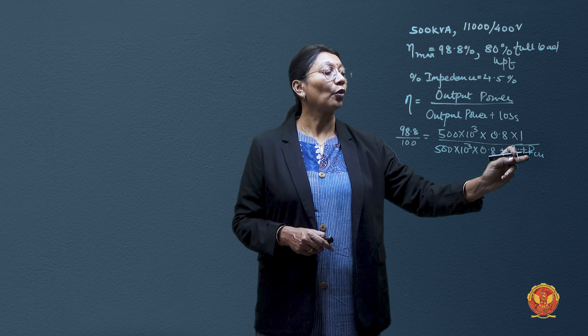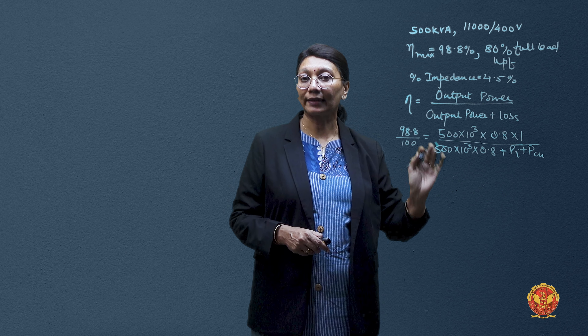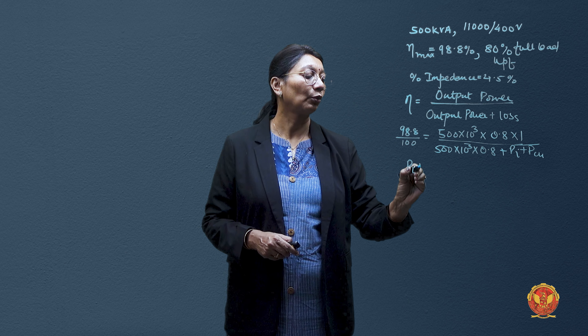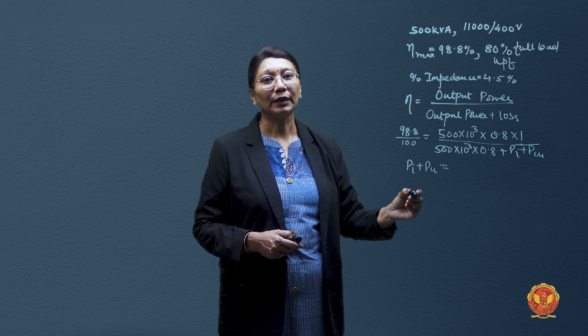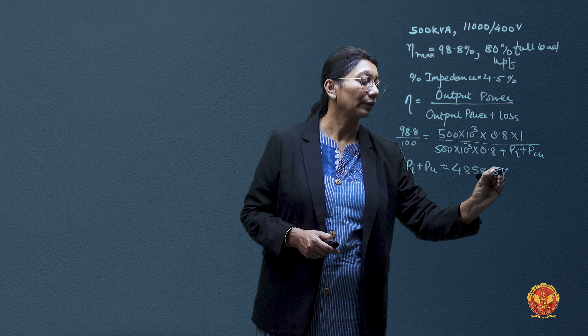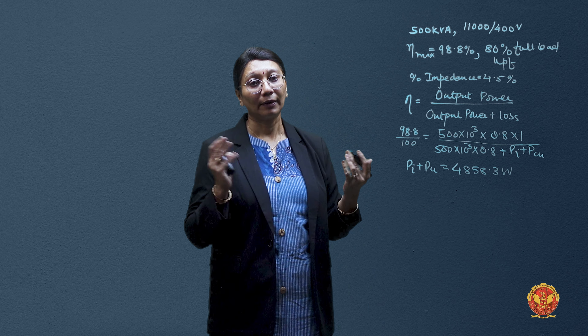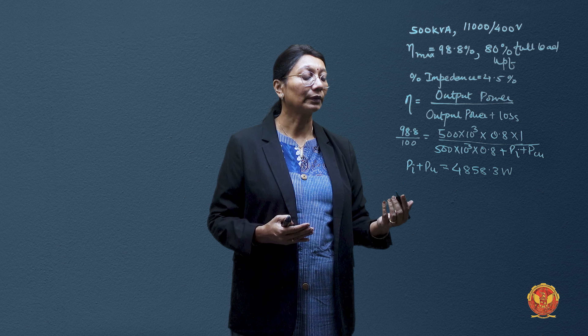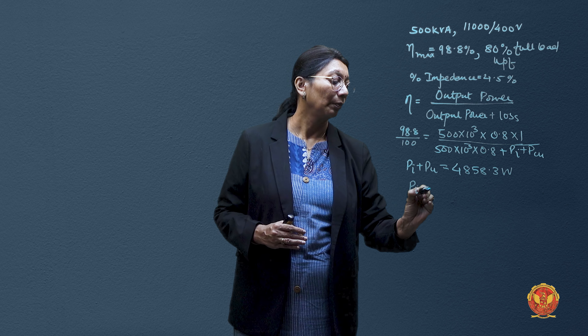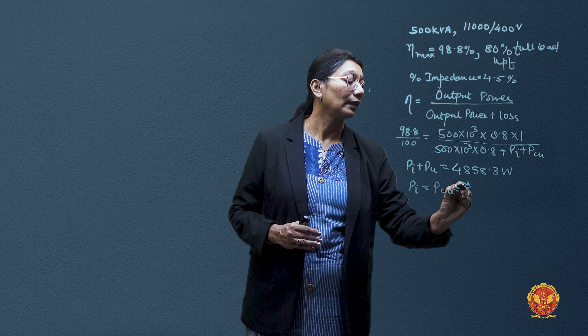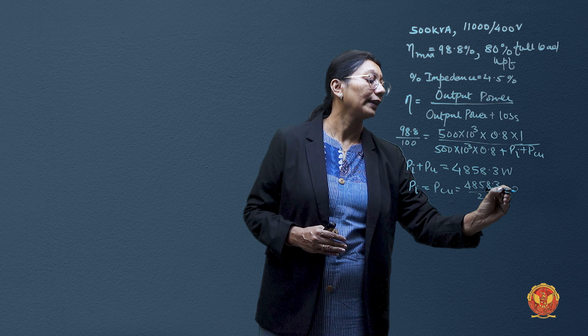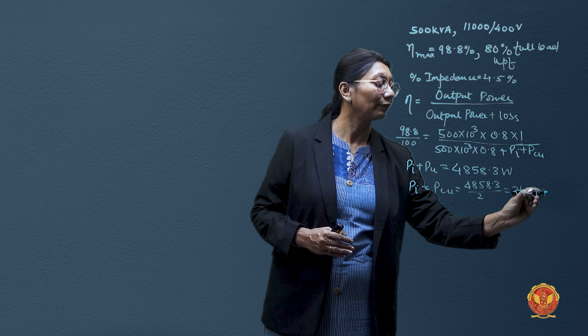At maximum efficiency, the copper losses include a factor of 0.8 (since x = 0.8 at 80% load). Solving, we get total losses of 4858.3 watts. At maximum efficiency, iron loss equals copper loss, so Pi = Pcopper = 4858.3 / 2 = 2429.15 watts.